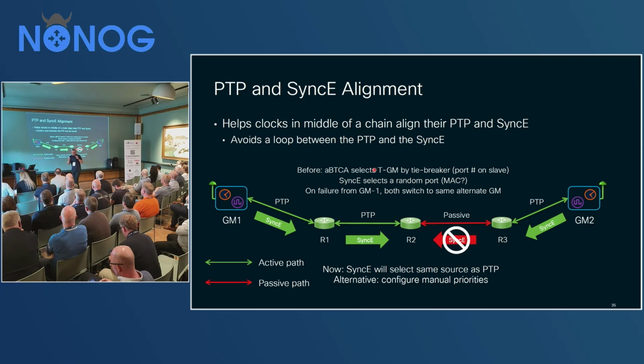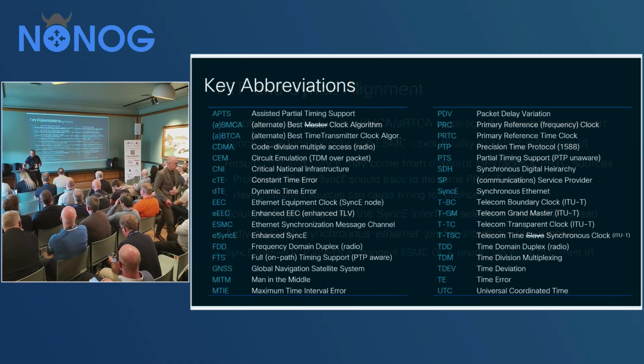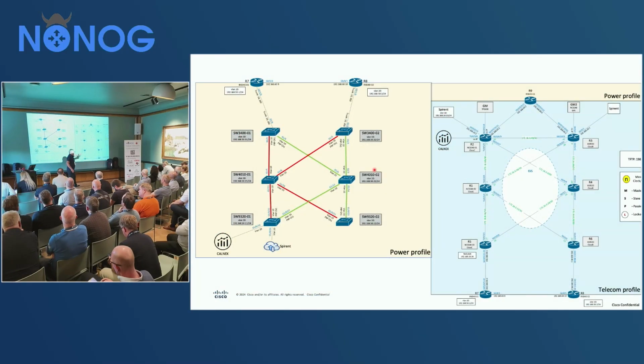And I can assure you, if you're working on PTP, this is one of the most important experiences. Going back to my topology, and I'm soon done. Looking at this one, if you get a failure in your network, so the entire network needs to converge, if you don't have control of this, I can almost guarantee that PTP will go into holdover state. The protection unit will then say, whoops, unusable clock, I will trip to protect my entire power grid. Or the mobile network will say, whoops, unusable clock, I will stop providing services for my mobile network.